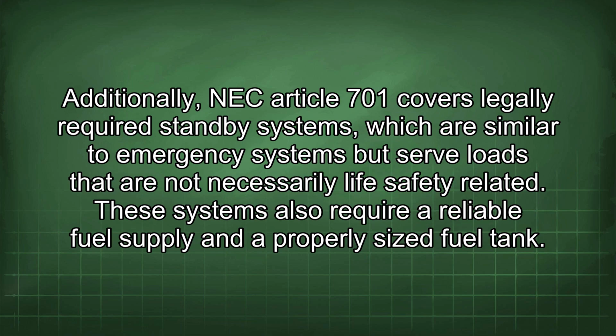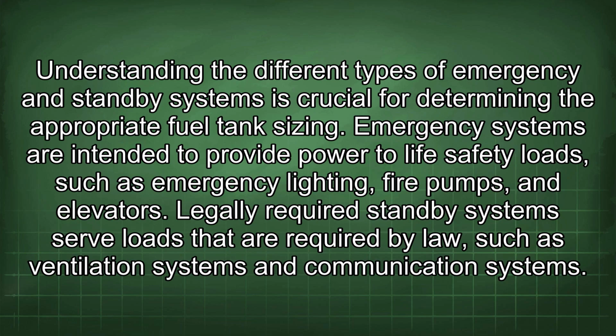Additionally, NEC Article 701 covers legally required standby systems, which are similar to emergency systems but serve loads that are not necessarily life safety related. These systems also require a reliable fuel supply and a properly sized fuel tank. Understanding the different types of emergency and standby systems is crucial for determining the appropriate fuel tank sizing.